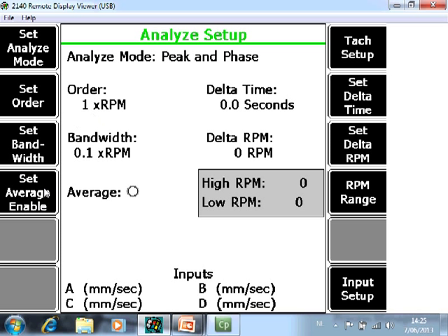F4 Set Average for normal run-out measurements or shutdown measurements. This feature has to be disabled because you want to see Peak and Phase measurements from any moment in time and not an averaged value.